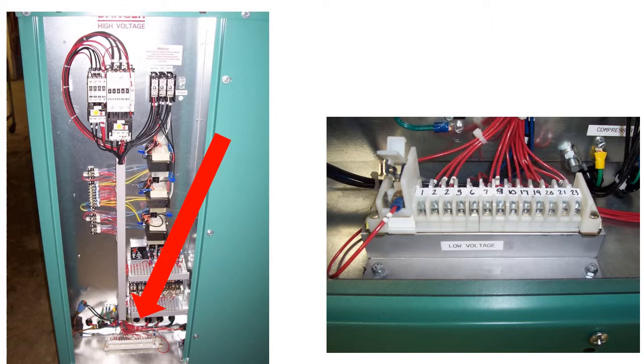All terminals with the same number are electrically identical. The 1s, or 1As, are the hot wire for the transformer and the 2s are the transformer's common.